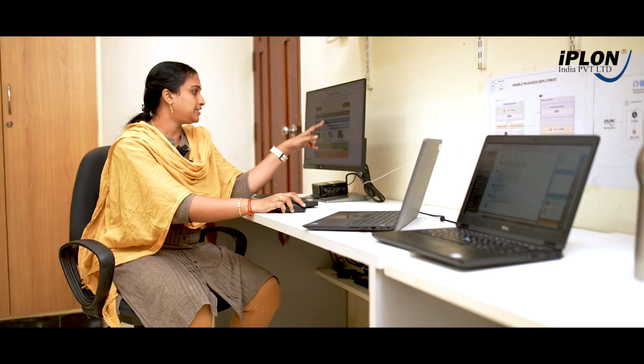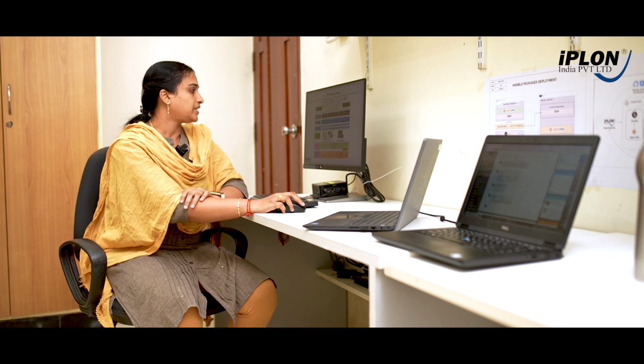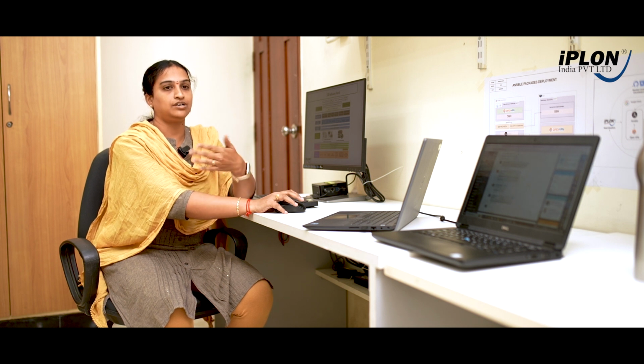And next comes the PPC controller. For communicating with the field devices or to control the field devices, PPC comes into the picture. According to CEA guidelines, all the configurations have been done for active power, reactive power, voltage and frequency controls. The algorithms are built to control the field devices for better handling of the devices, and also to keep the grid parameters stable.